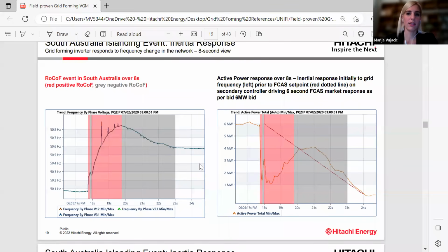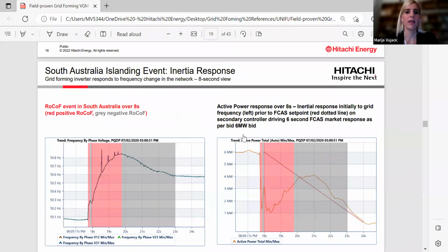Okay, the next demonstrated capability was the inertia response of the battery energy storage system. This was a real event, when the South Australian state separated from the nearby state. What we can see here is how the active power response mirrors the rate of change of frequency (RoCoF) event. What you can see shaded in red here is the positive RoCoF, which resulted in reduced active power output, while the gray shows the negative RoCoF, which resulted in an increase of the active power.